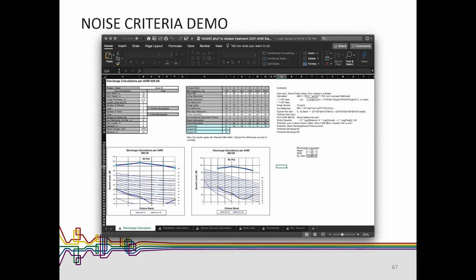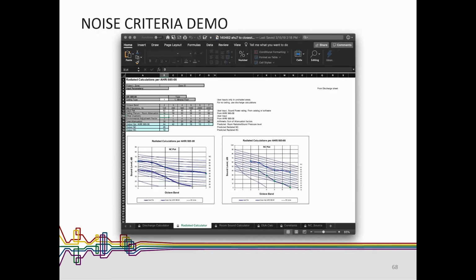But anyway, what you do with this is plug in your duct size on the left-hand side, whether it has lining, how many elbows, how many tees, what it takes to get to the first room that's going to be affected. In the middle, it tells us how much reduction we're getting for each of those items. The bottom tells us how much sound is getting to the space, up to the edge of the space.